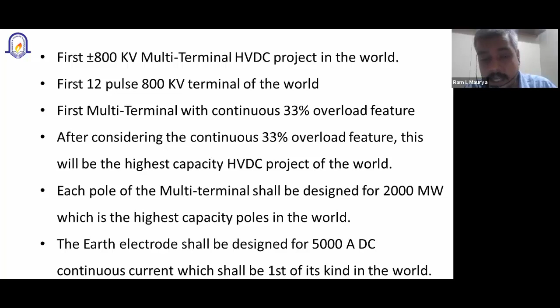Some other projects: Mumbai is also a power hungry city. There is the Chandrapur Padga Bhivandi line, approximately 762 kilometers from Chandrapur, because the super thermal power plant is there. Then there is the Rihand Dadri line, and the 250 megawatt HVDC Vindhyachal back-to-back station. A back-to-back station is only for synchronizing 2 different grids. If you cannot connect two grids directly, then an HVDC back-to-back station is used.